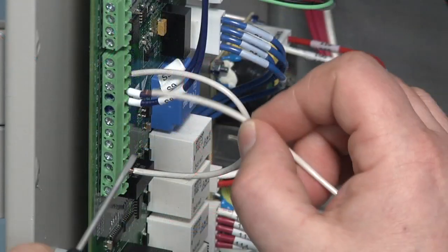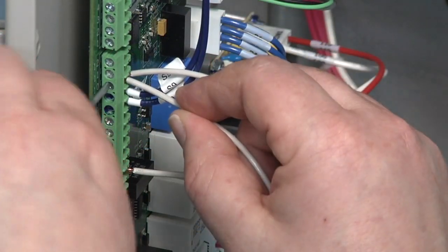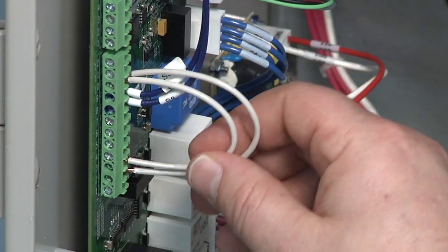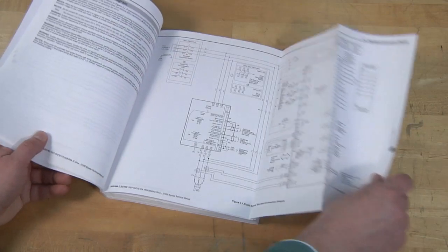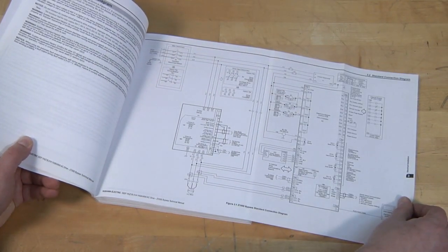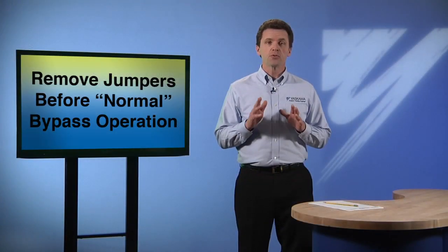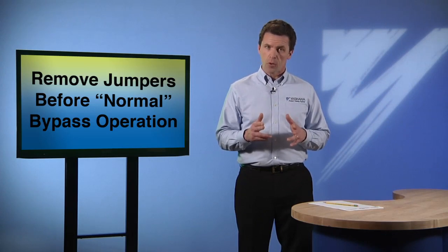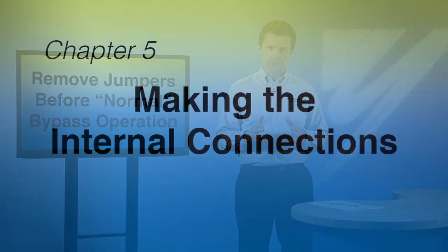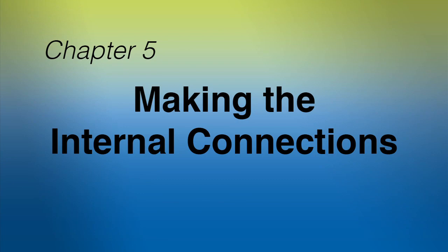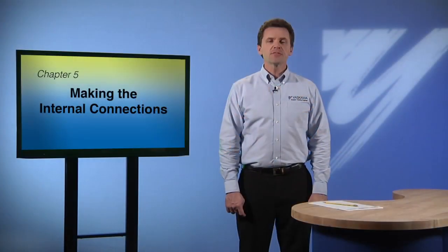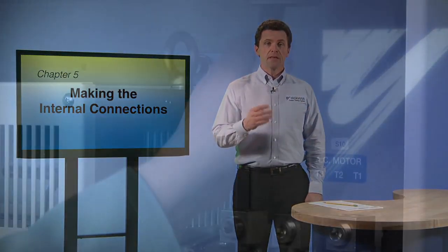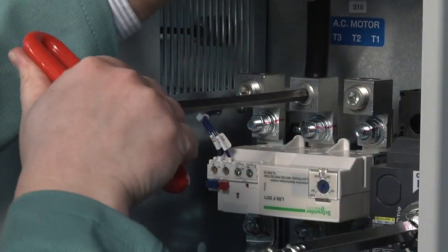Either attach a set of normally closed safety contacts here, or apply a set of jumpers. If you choose to apply jumpers, your technical manual will guide you to the terminals to use. When we're finished, it's very important to remove the jumpers before beginning normal bypass operation. Let's make some connections. Begin by attaching our motor leads to the motor overload.